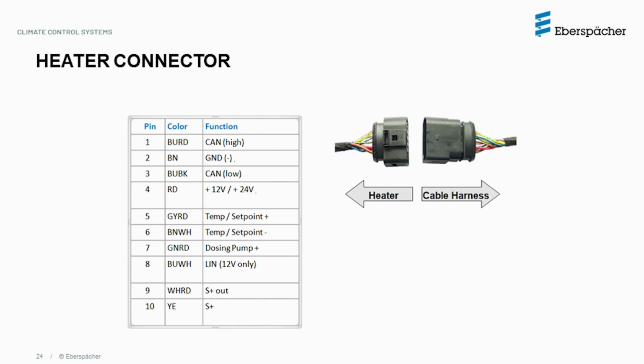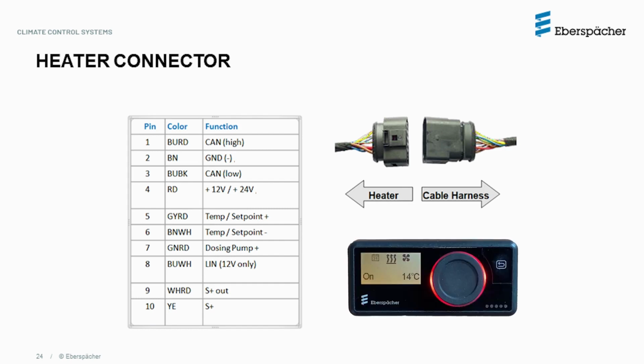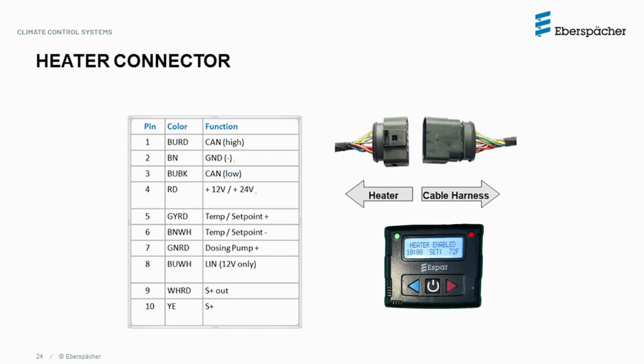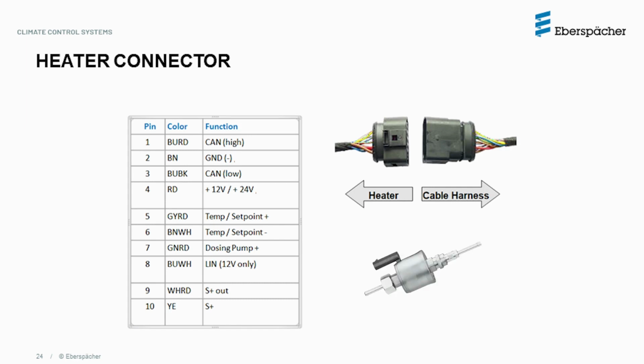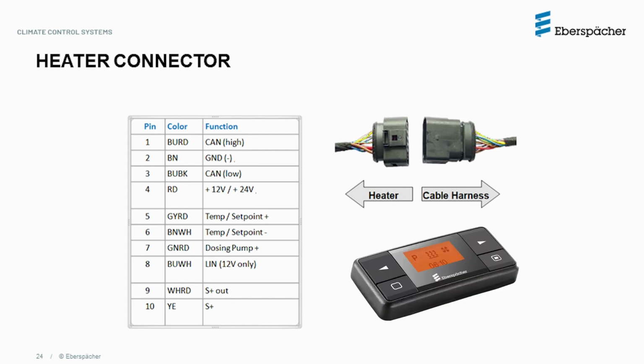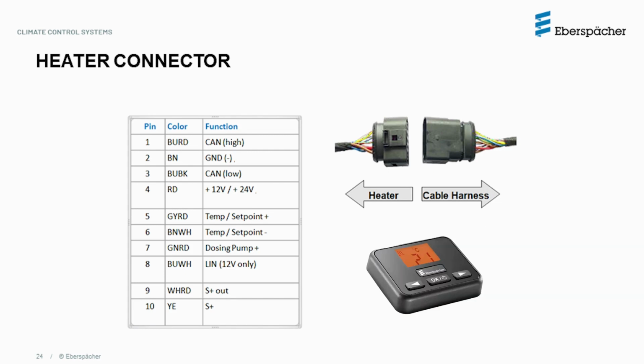Pins 5 and 6 have dual purposes. If the Easy Start Pro controller is being used, then pins 5 and 6 could be used for an external sensor on the heater side. But when an analog controller like the Digimax is being used, then pins 5 and 6 are reserved for set point temperature connections. Pin 7 is used to send pulse signals to the fuel metering pump.